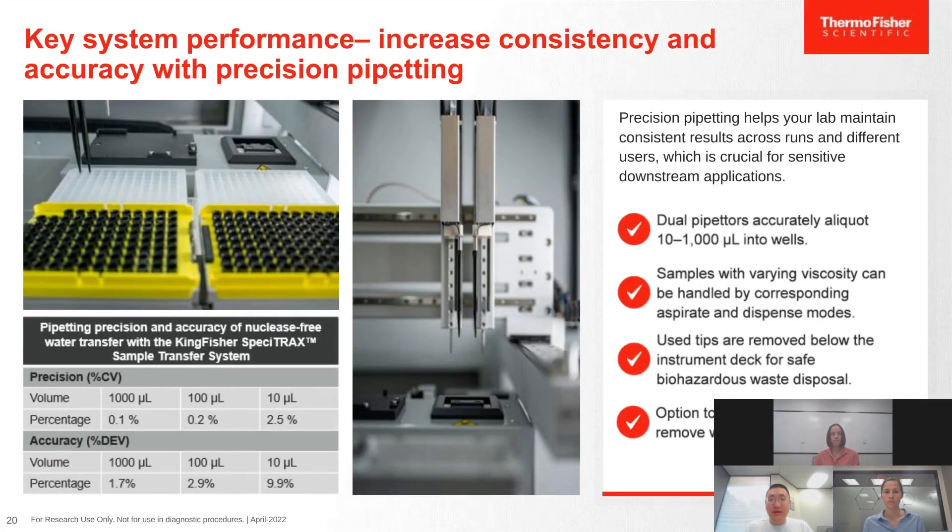The system features dual pipettors capable of aliquoting 10 to 1,000 microliters of samples into wells. Samples with varying viscosities can be handled with corresponding aspiration and dispense modes, easily selectable in the software. Used tips are ejected below the instrument into biohazard waste for safe disposal. The table shows precision and accuracy metrics for the system across the 10 to 1,000 microliter range.